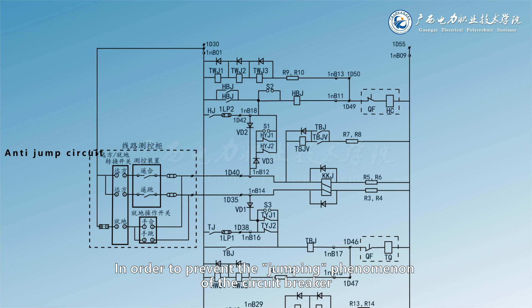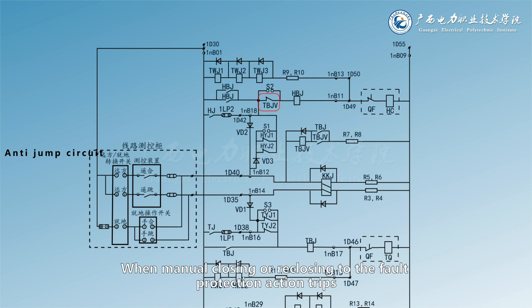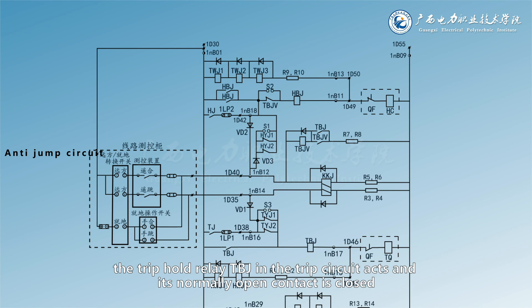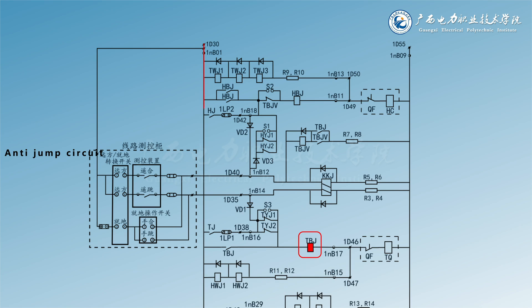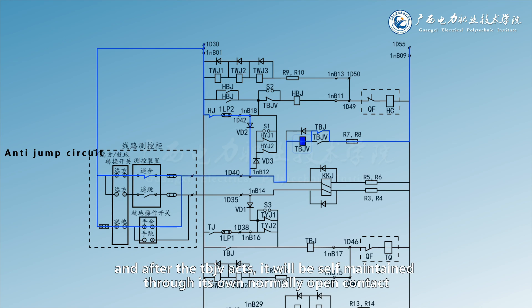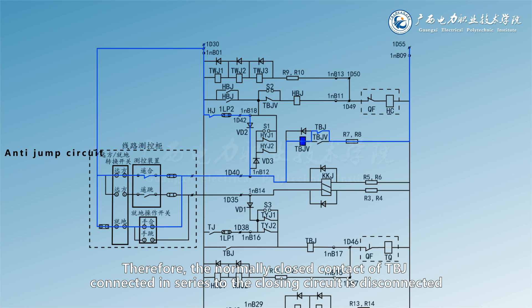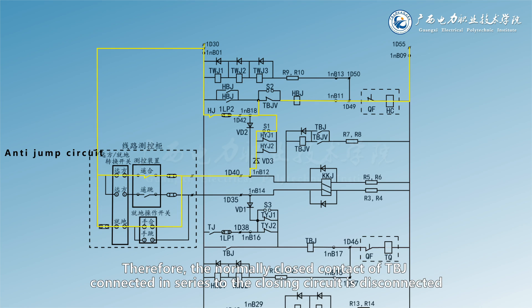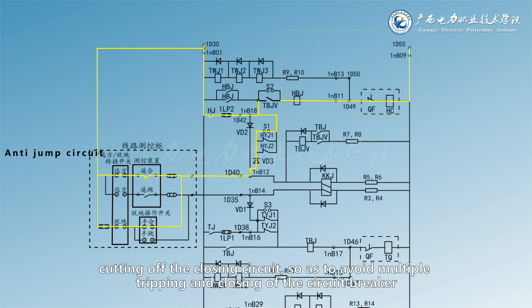In order to prevent the jumping phenomenon of the circuit breaker, an anti-tripping circuit is set in the operation circuit. When manual closing or reclosing to a fault causes protection action to trip, the trip hold relay TBJ in the trip circuit acts and its normally open contact is closed. When the closing pulse is not released, the closed TBJ normally open contact will make the anti-tripping relay TBJV act, and after TBJV acts, it will be self-maintained through its own normally open contact. Therefore, the normally closed contact of TBJV connected in series to the closing circuit is disconnected, cutting off the closing circuit so as to avoid multiple tripping and closing of the circuit breaker.